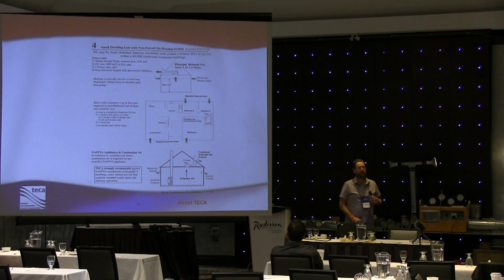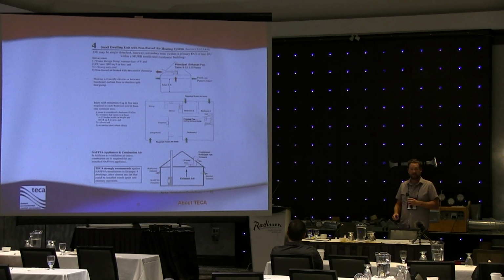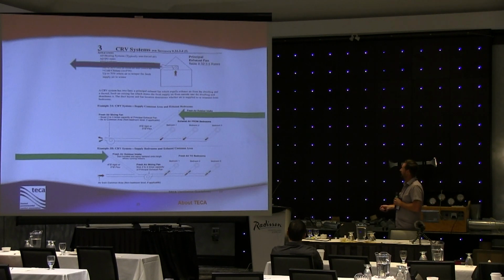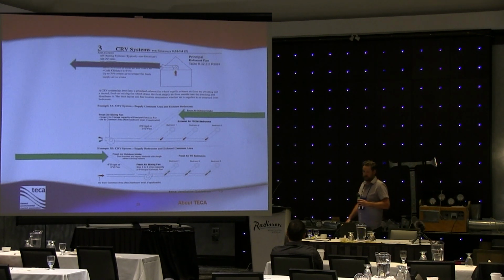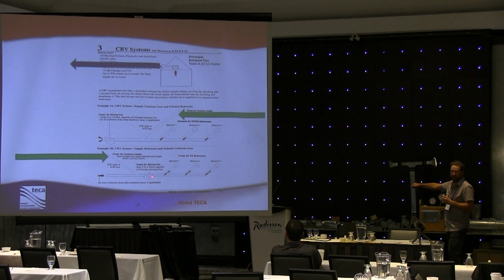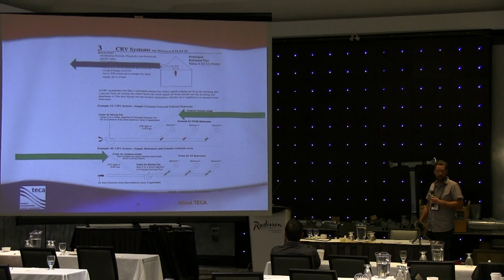The CRV system where you're putting air into the vent. Yes. The code doesn't address it. Is there a recommended length where you're mixing the air before it gets to the outlets? Actually, in here we talk about it. The recommended length for this ductwork. Is that what you're talking about? No, from where the 2 mix together to the actual outlets in here. You know, the code is pretty silent on that. It doesn't prescribe exactly how to set up this ventilation system, but I hear what you're saying. If this connection was right off of the fan collar for the first bedroom, that bedroom would get probably 90% of the air, and further down the ductwork, if these are quite a bit further away, they would get far less. So it doesn't get a chance to mix as much. Doesn't get a chance to mix as much, exactly.